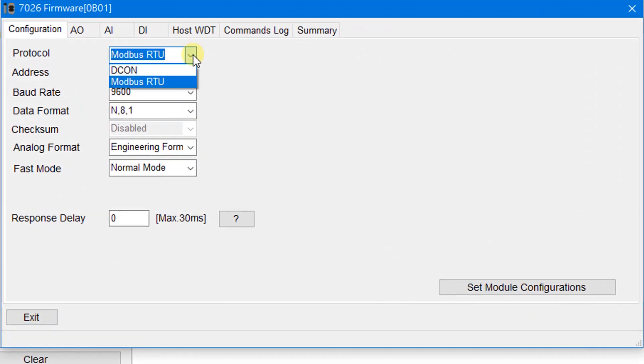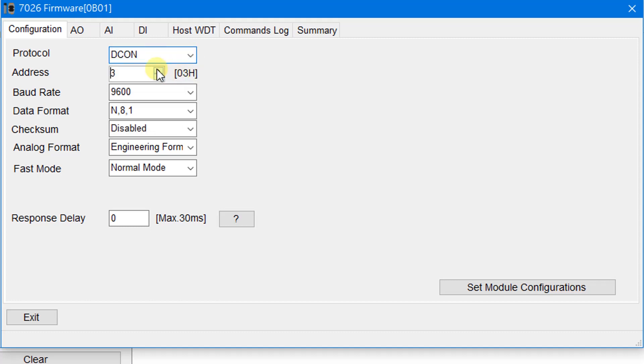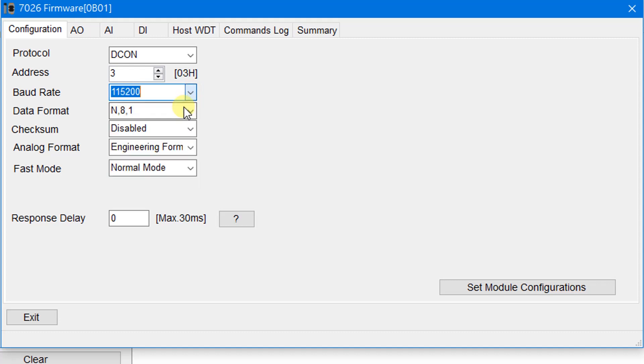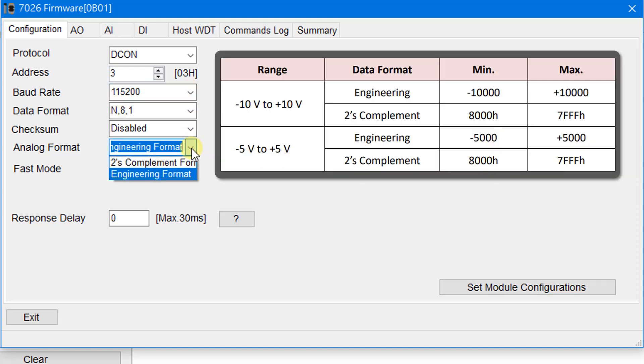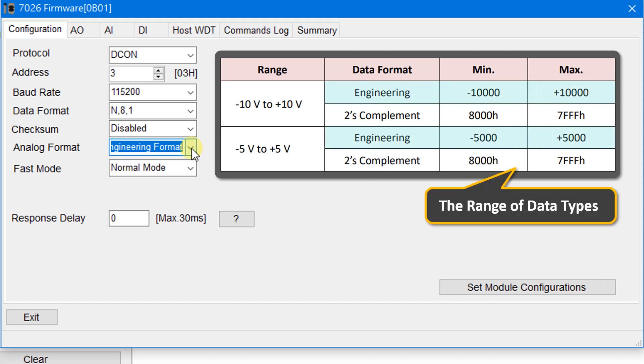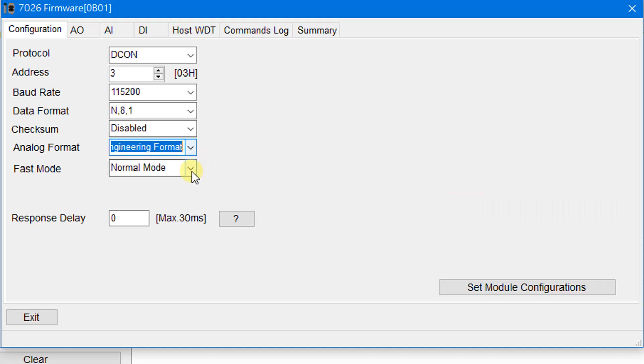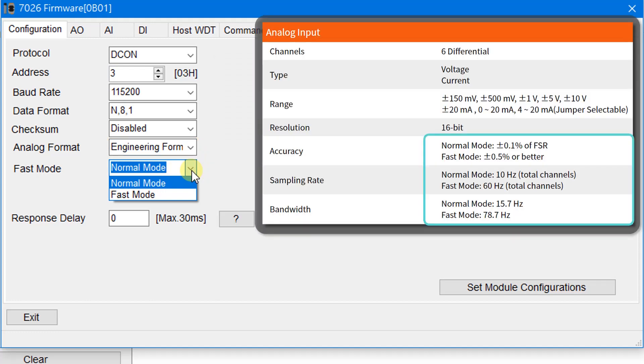The M7000 series module supports DCON and Modbus protocols. In this case, set the protocol to DCON, the address to 3, and the baud rate to 115200. Set the analog format to engineering format — the ranges of data types can be found in the user manual. Set the fast mode to normal mode; the product page shows that the sample rate in normal mode is 10 Hz for the total channels.